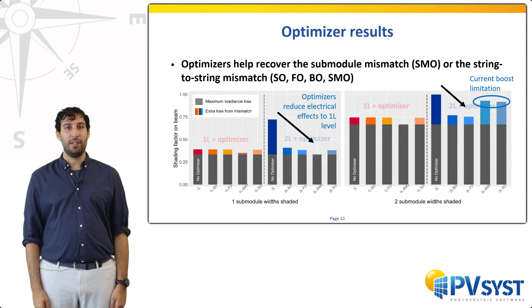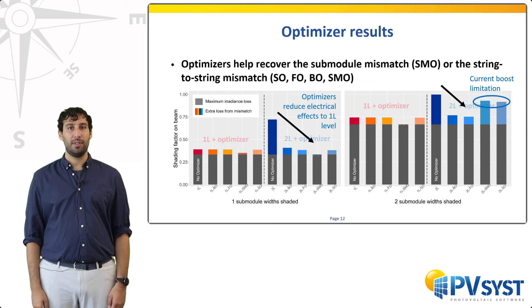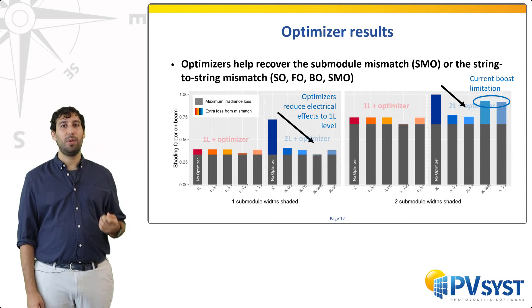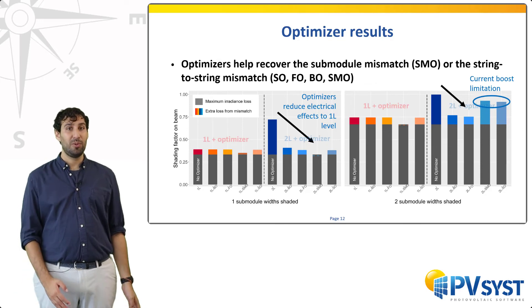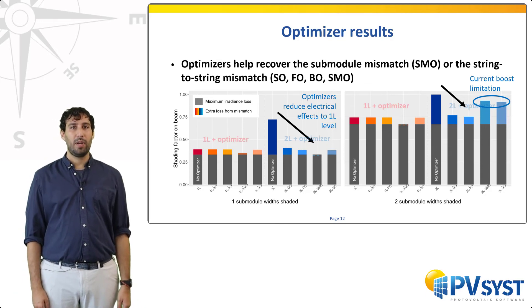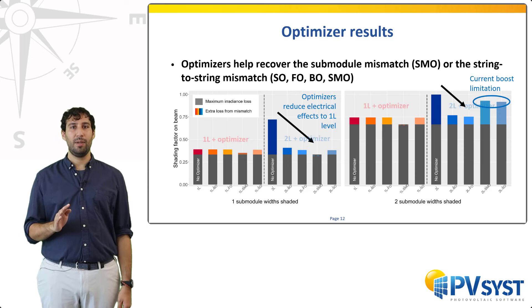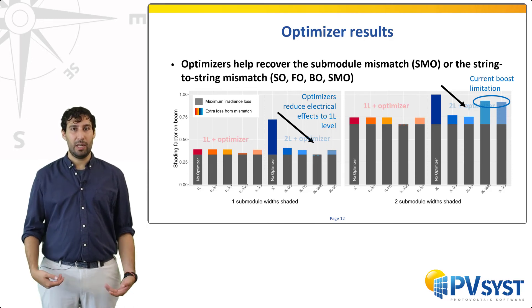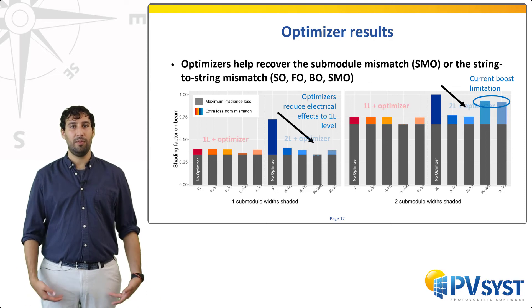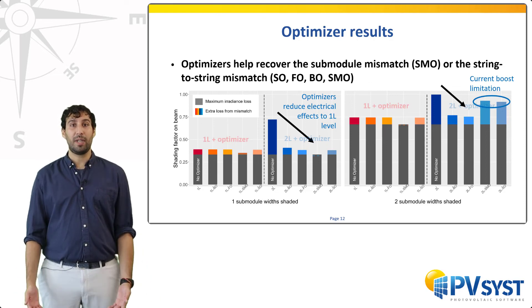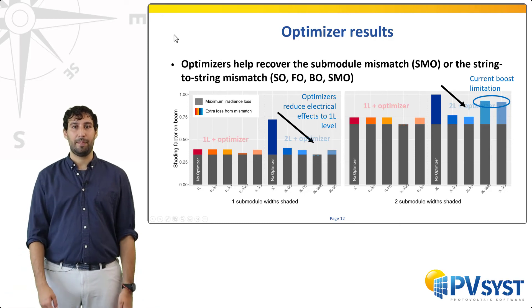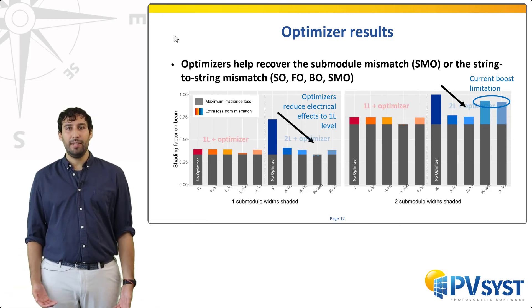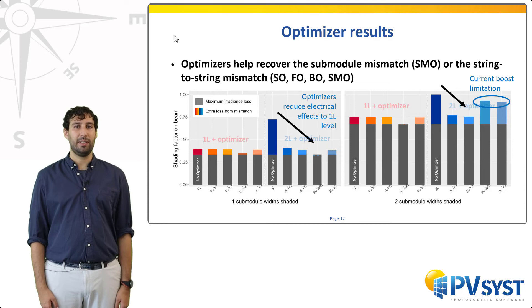Finally, once the shadings and therefore the mismatch become important — for example when two sub-modules are shaded — the optimizers may start to show their limits. You can see this for cases 2L-SMO and 2L-SO. This is because there is a limit to the current boost and voltage boost that the optimizers can provide, and the optimizers used in this study hit that limit. In these cases, the mitigation is not as effective.